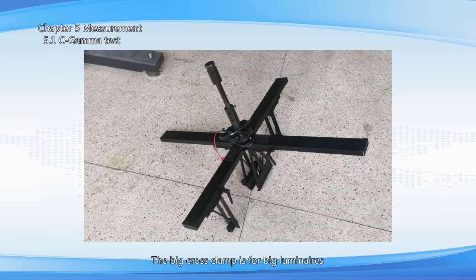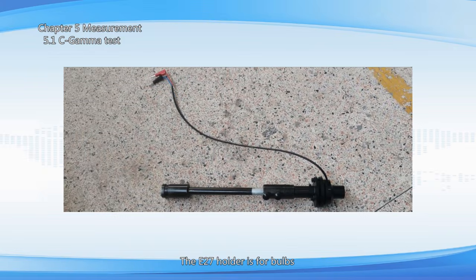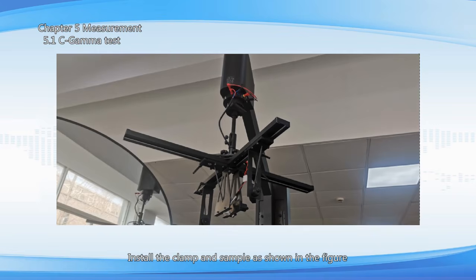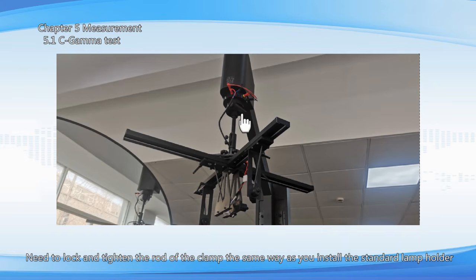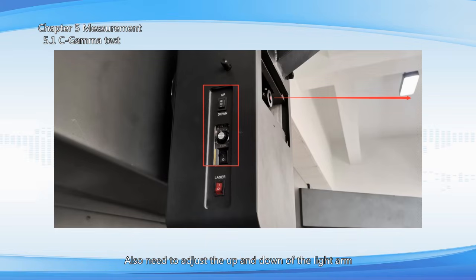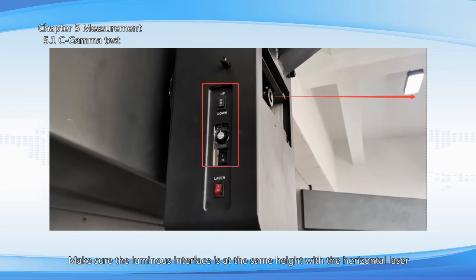C gamma test. LISUN provides 2 clamps for the C gamma test. The big cross clamp is for big luminaires. The E27 holder is for bulbs. Install the clamp and sample as shown in the figure. The luminous interface of the lamp should be in the center of the clamp. You need to lock and tighten the rod of the clamp the same way as you install the standard lamp holder. Also adjust the up and down of the light arm. Make sure the luminous interface is at the same height as the horizontal laser.